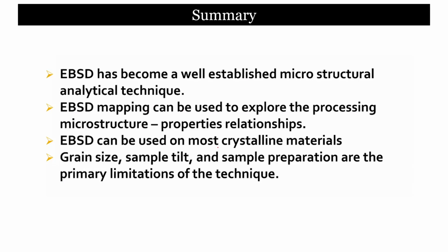EBSD can be used on most crystalline materials. The grain size, the sample tilt, the sample preparation are the primary limitations of the technique. The sample preparation, because you should have a specific thickness of your specimen to have the Kikuchi pattern, and for that you need certain sample preparation techniques. And the sample tilting, you need a very high degree, that is 70-degree tilt in your specimen to get the EBSD pattern.